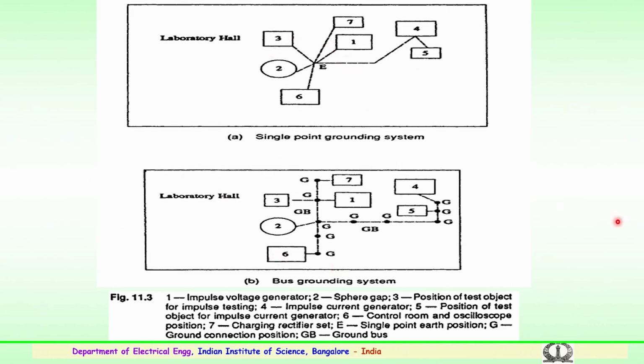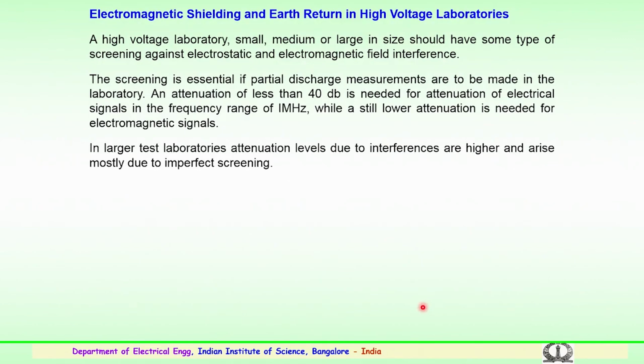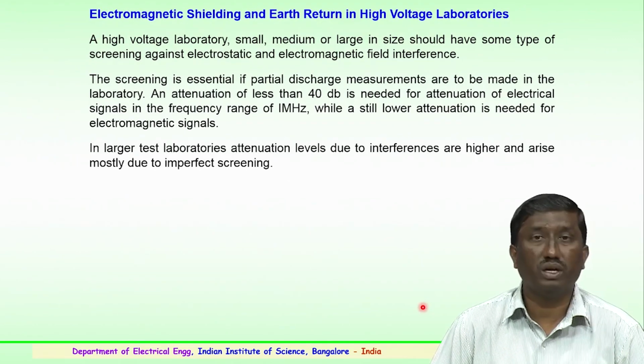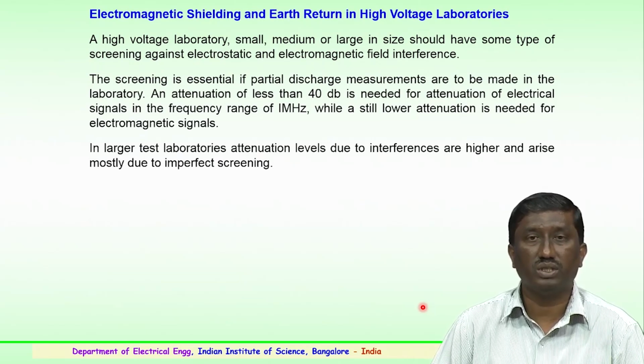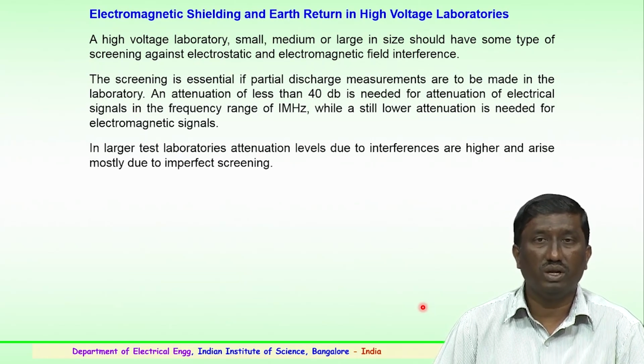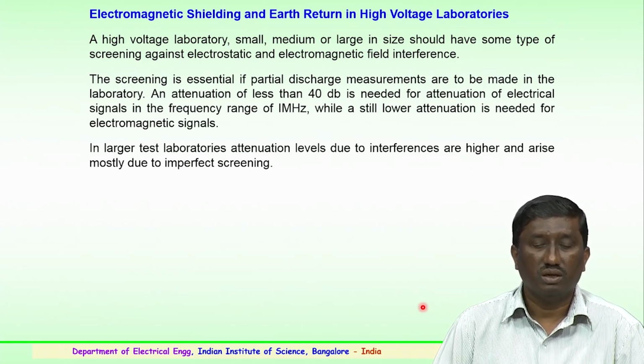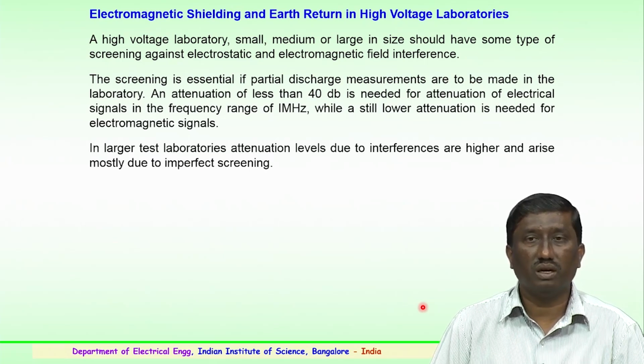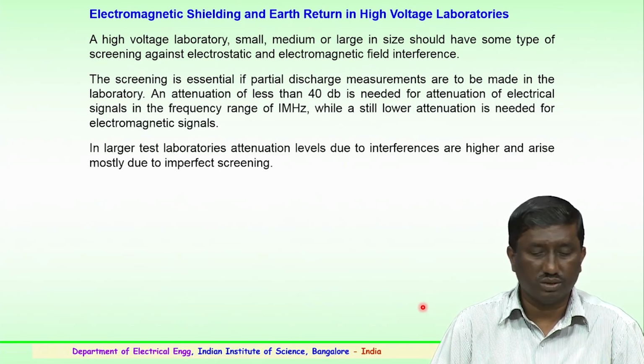So, the importance of either going in for a single point grounding or a bus grounding is to see that the rise of potential is brought down, and the equipments which are under test and also which are to be tested are properly grounded. The importance of electromagnetic shielding and earth return in a high voltage laboratory is also essential, a very important point. So, any high voltage lab, whether a small, a medium or a large size laboratory, should have some type of screening against the electrostatic and electromagnetic field interferences which could be caused by external sources.